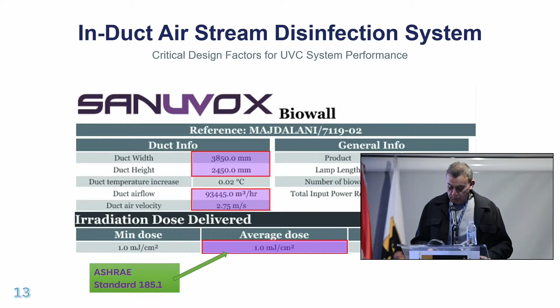Also, the dosage that is required for airstream disinfection is found in the ASHRAE 185.1. This ASHRAE standard is different than the ASHRAE standard for the coil disinfection. The coil disinfection talks about surface disinfection. It's 185.2. 185.1 talks about the airstream disinfection. This dosage is actually indicated in these codes. So we plug in all these numbers. We get an output that we need 2 batteries of lights. Each one is 76.2 centimeters long.